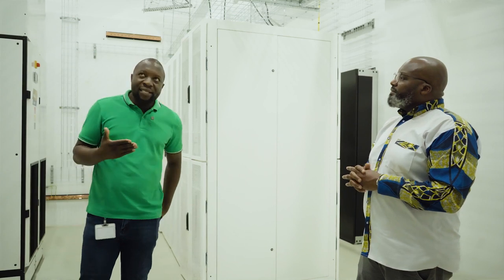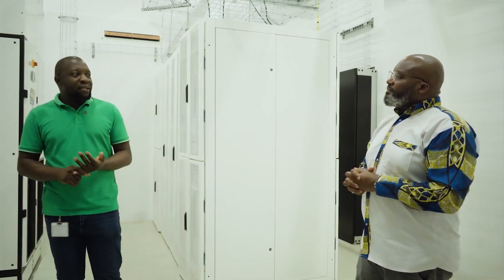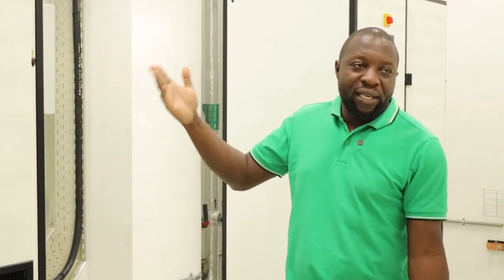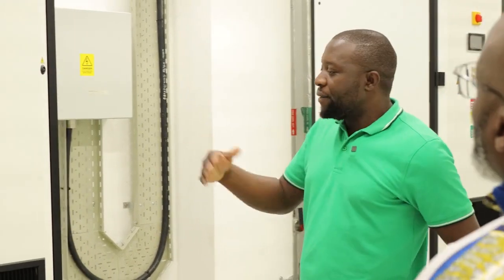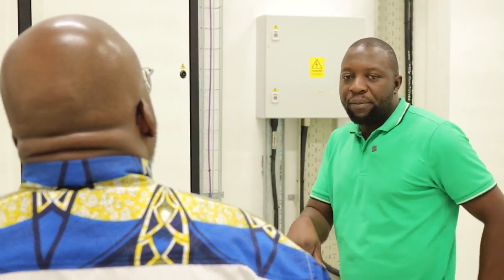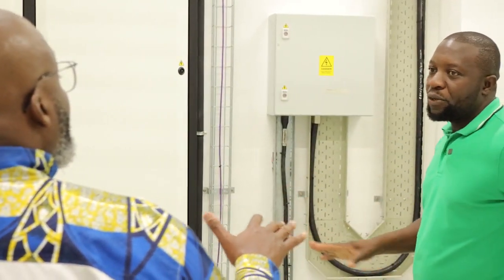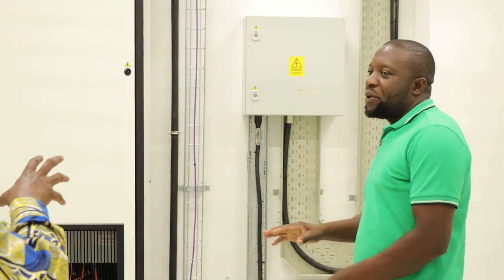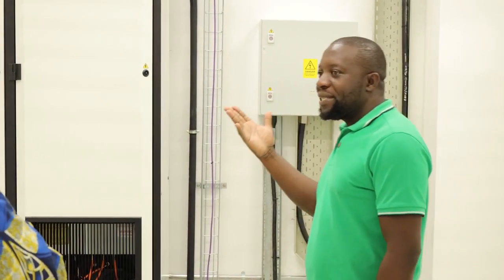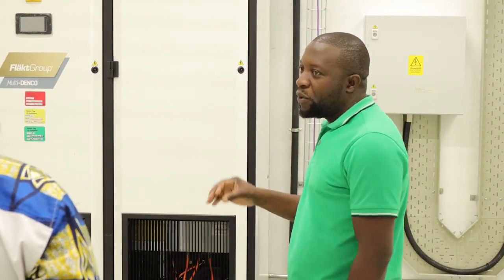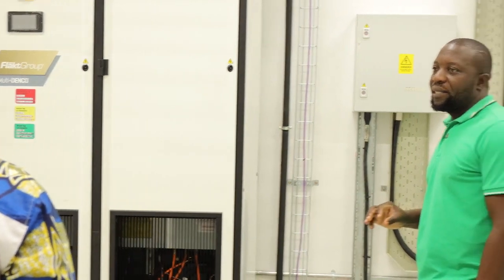Yes. On colder days, maybe when the temperature is around 19, because if we have a temperature difference of 5 degrees Celsius between the required temperature in this room and the ambient temperature outside, then the free cooling will kick in. It will start cooling this particular room. And this is automatic? It's automatic. No one has to go in. No one has to go in, yes. Wow. When the ambient temperature rises, then the DX system will kick in. So that means it's very efficient in terms of cooling. We're able to save power consumed in cooling this facility.